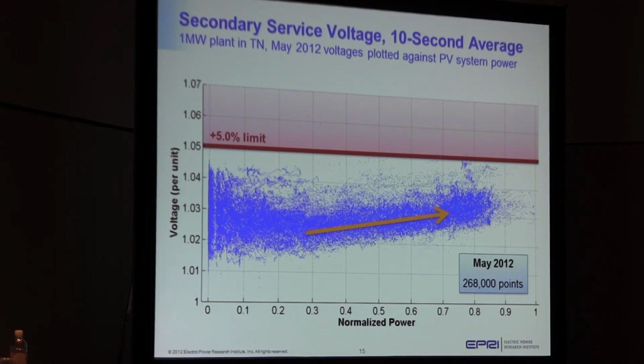We plotted 10-second average voltage against power. You can see at nighttime you have 0 power, and the voltage can range quite a bit, nominally 1.01 up to 1.04 or greater. As the PV system output increases, you can see a direct correlation: the more PV you're generating, the higher you're going to push that voltage up. And that's what we would expect given the electrical phenomenon.